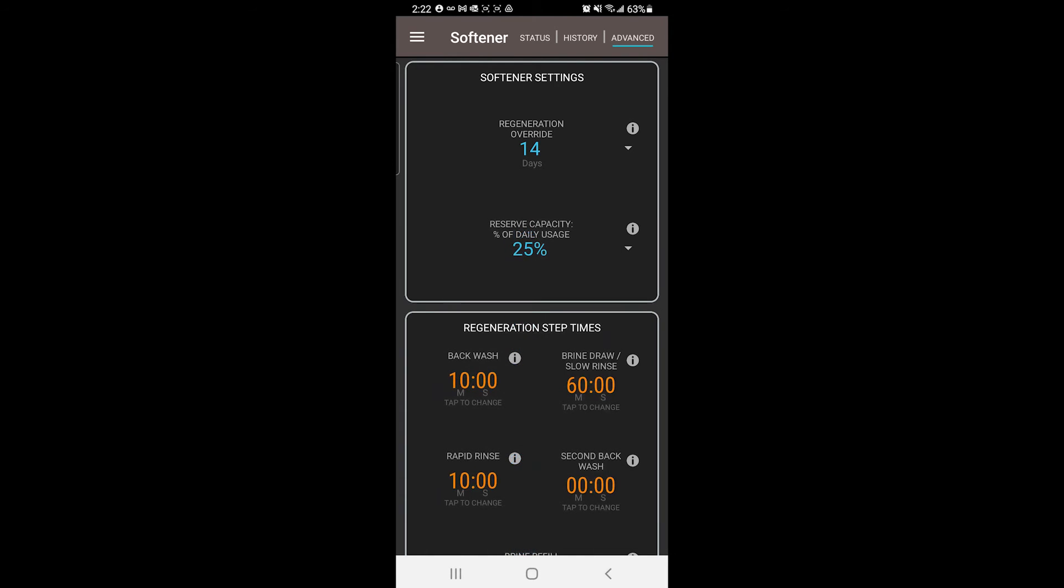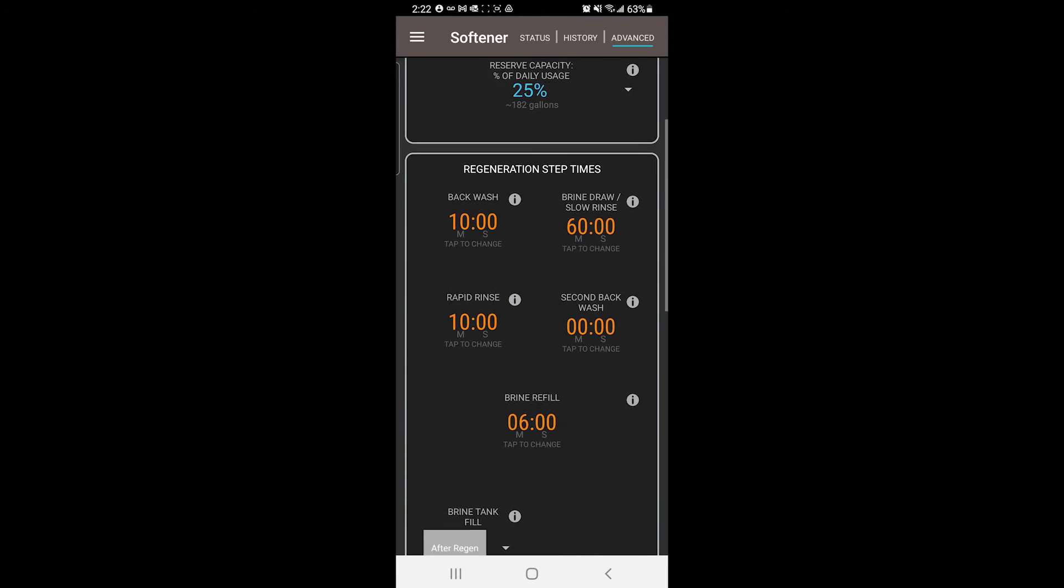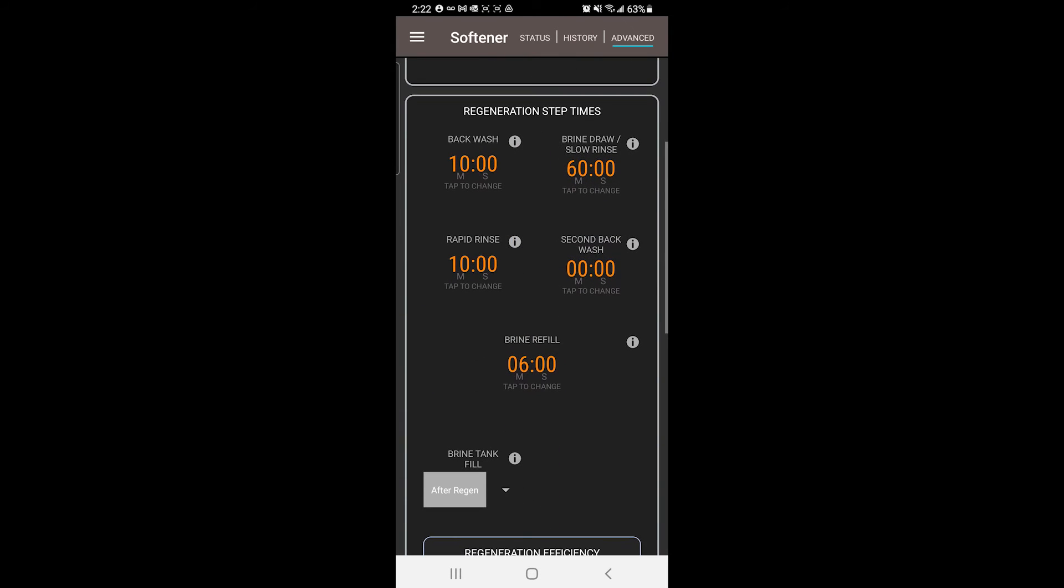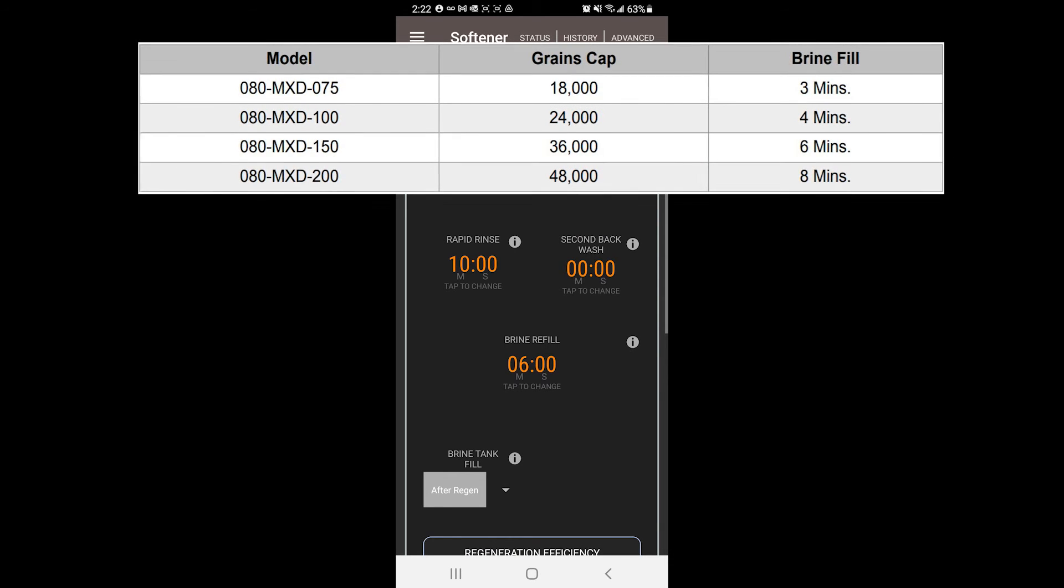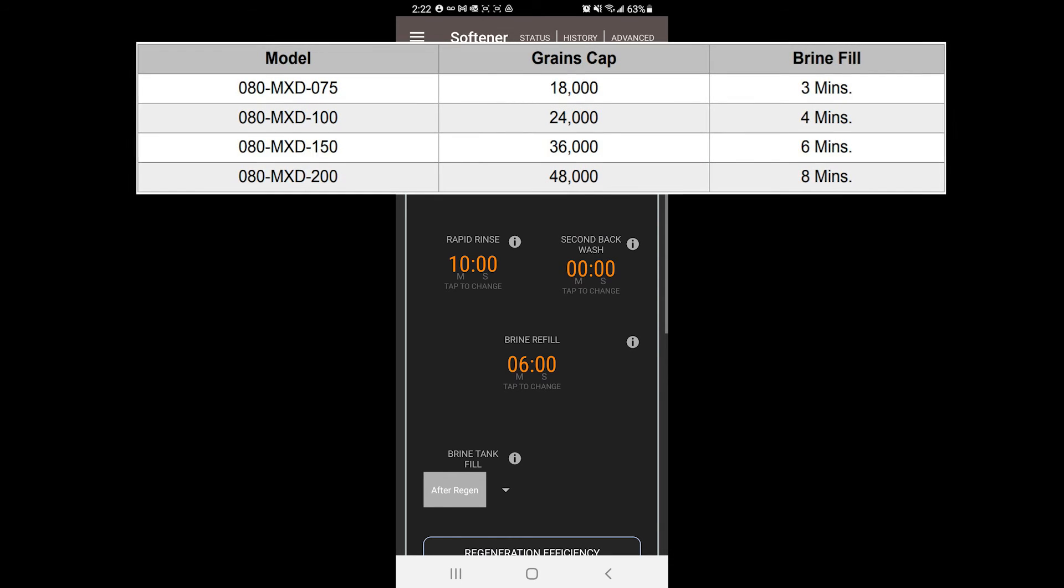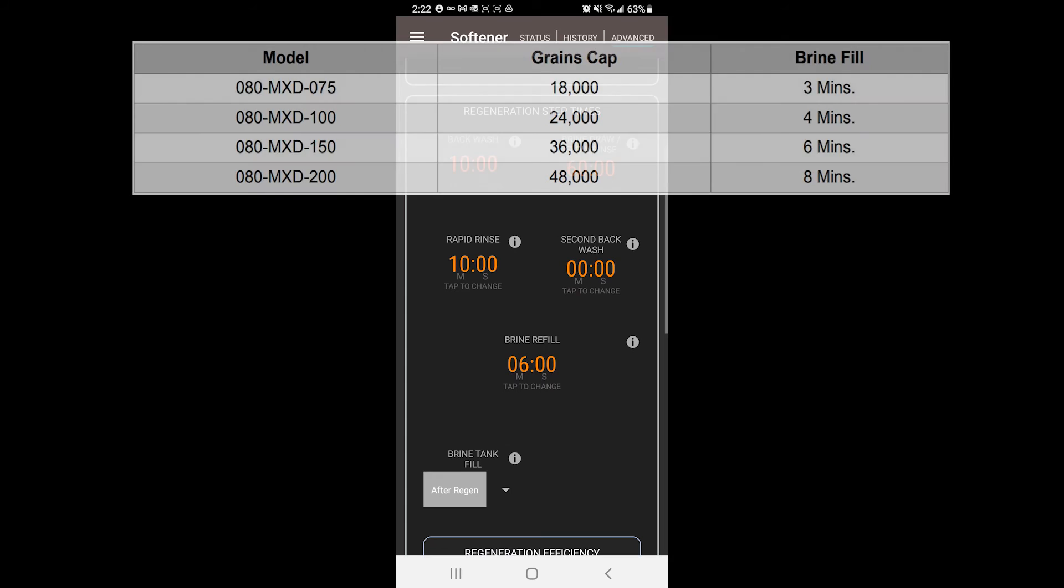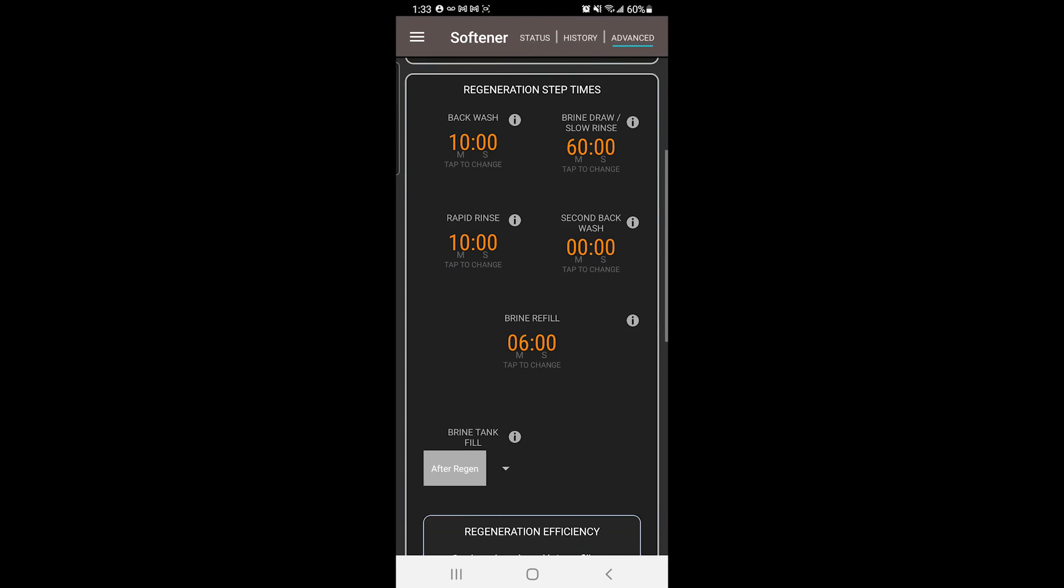Other settings should look like this. Backwash is set to 10 minutes. Brine Draw Slow Rinse is set to 60 seconds. Second Backwash is set to 0 minutes. Rapid Rinse is set to 10 minutes. And brine refill is set to 3, 4, 6 or 8 minutes depending on the model softener you purchased.